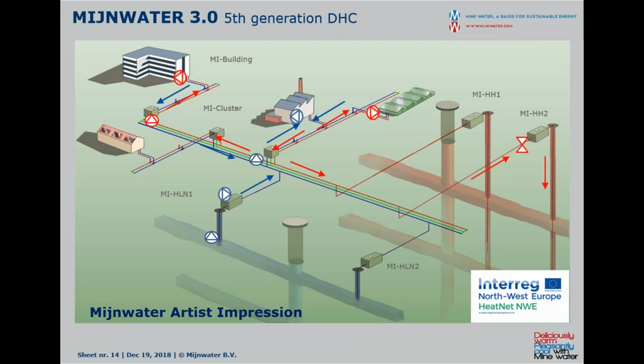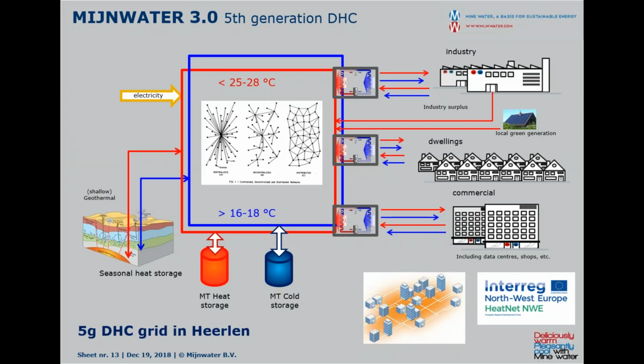Those heat pumps that we are running, fed by water from 25 to 28 degrees, have a very high performance. They have COPs of 5, 6, or 7, and as I said, if we give heat, we produce cold at the backside and bring it into the cold circuit. So if your neighbor has a cold demand, then even the backside of the heat pump is raising the COP of this energy flow.